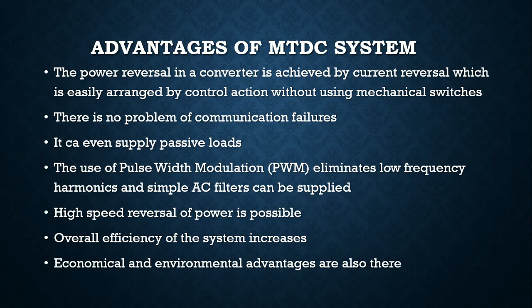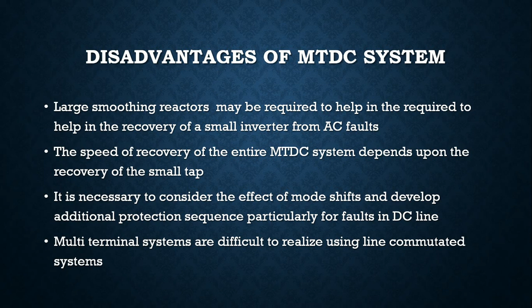Let us see about some of the disadvantages of MTDC systems. Large smoothing reactors may be required to help in the recovery of a small inverter from AC faults. The speed of recovery of the entire MTDC system depends upon the recovery of the small tap. As we said, the MTDC system is based on the tapping, so if we need a recovery of the entire MTDC system, it needs a recovery of that small tapping. It is necessary to consider the effect of mode shift and develop additional protection sequences, particularly for faults in the DC line. Multi-terminal systems are difficult to realize using line commutated systems.